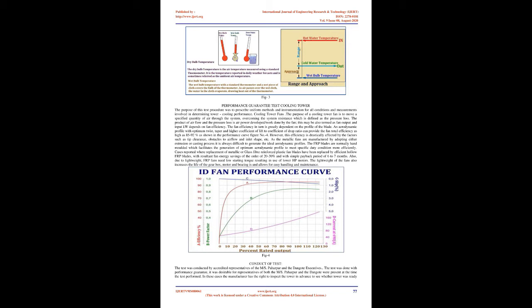Crossflow induced draft. In the counterflow induced draft design, hot water enters at the top, while the air is introduced at the bottom and exits at the top. Both forced and induced draft fans are used. In crossflow induced draft towers, the water enters at the top and passes over the fill. The air, however, is introduced at the side, either on one side, single flow tower, or opposite sides, double flow tower. An induced draft fan draws the air across the wetted fill and expels it through the top of the structure.